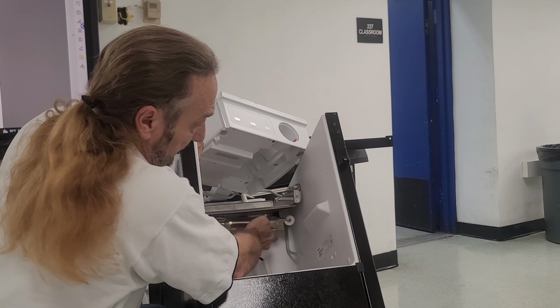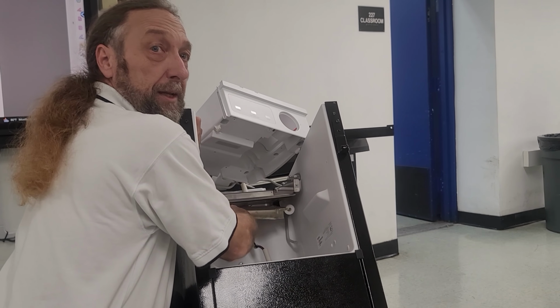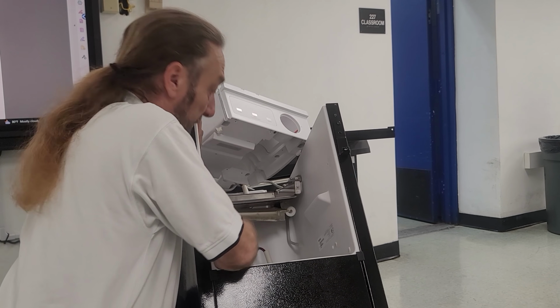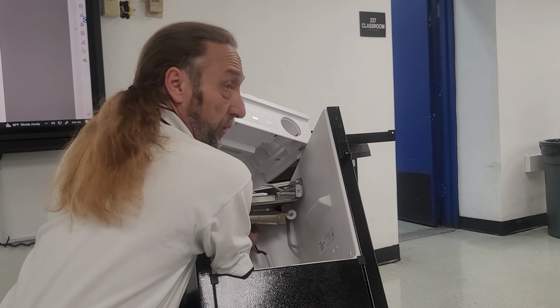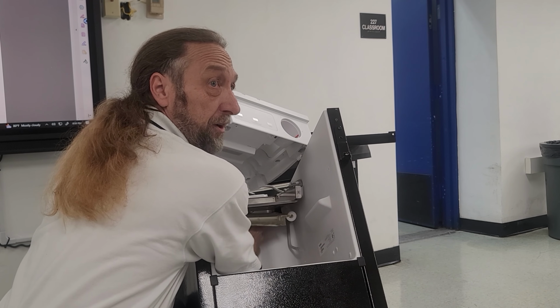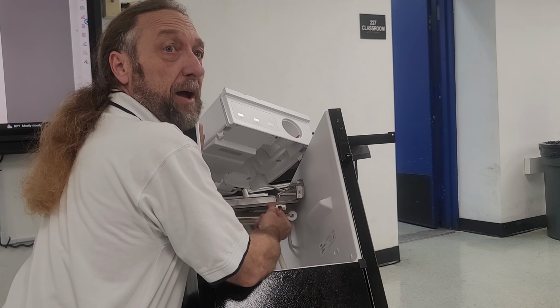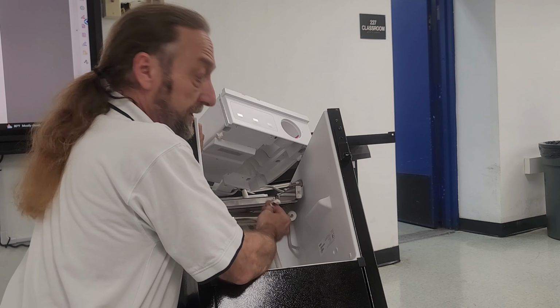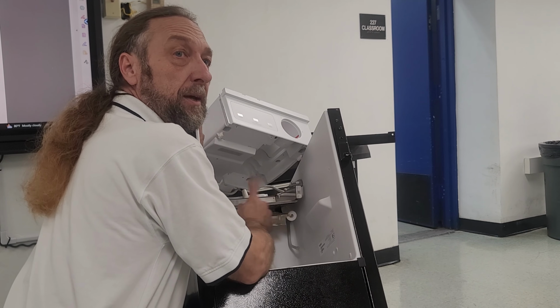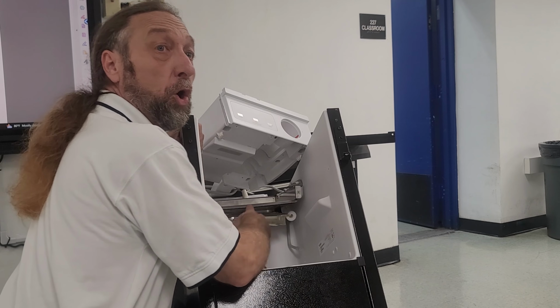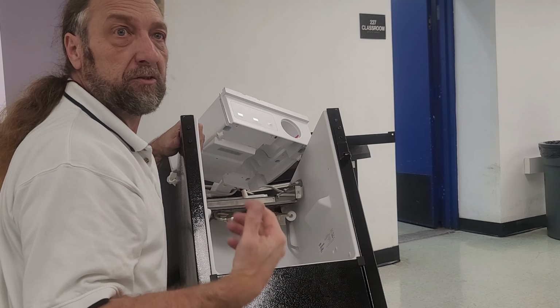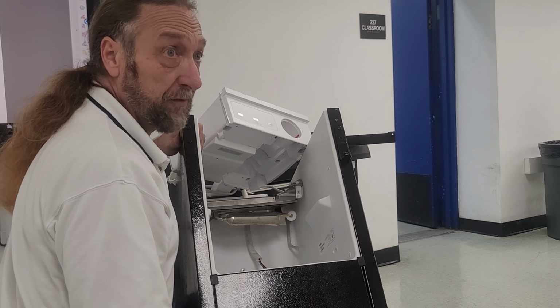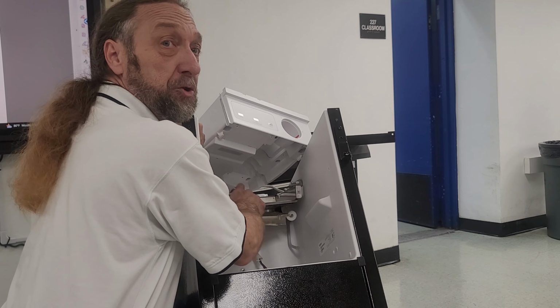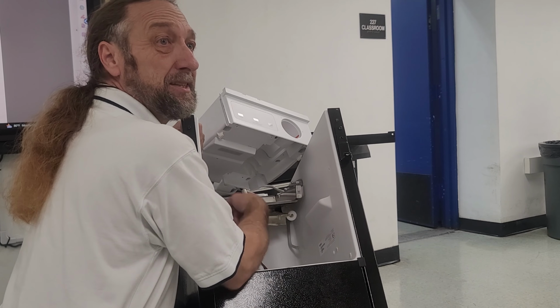This is the underside, this is actually the evaporator tubing here. Even though this is called the evaporator, the freon's running through tubing underneath. Right here in this area of the suction line is the evaporator thermistor. This is what's telling the unit the temperature of the evaporator. So when it goes to re-drop the ice, remember that the hot gas valve down there is pumping the hot refrigerant up here. This is sensing the hot refrigerant.